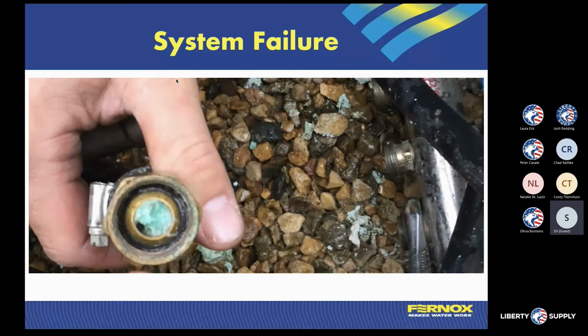It doesn't stop at the heat exchanger. So when you get out into the system, you'll see in different applications such as valves and different components, that there was a leak at one point, and sometimes you'll see different applications such as a copper piping system where you have kind of an aqua color across that system. That's what happened here. We had some eroding or corroding copper pipe, plugged up a snow melt system, and then the system stopped flowing. So then we couldn't obviously do the proper job that we were looking to do for that system. It just plugged up with the sludge and the breakdown of that copper piping system.